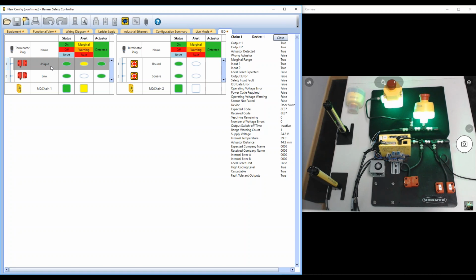That's correct. The switches we're using here are RFID based, so there's no mechanical moving parts like a reed switch or mag switch. There's a couple advantages for RFID. The first, as you mentioned, is the ability to handle vibration - since there's no moving parts inside, this does not have that problem. Another is if you have metallic shavings in a certain type of application, a mag switch would not be a great choice. And the other thing is, you see the 14.2 millimeters - an RFID switch has over two times the misalignment tolerance of a mag switch. With a mag switch you're looking at 5 to 7 millimeters, where with RFID you're going to get 10 to 14 millimeter misalignment tolerance.